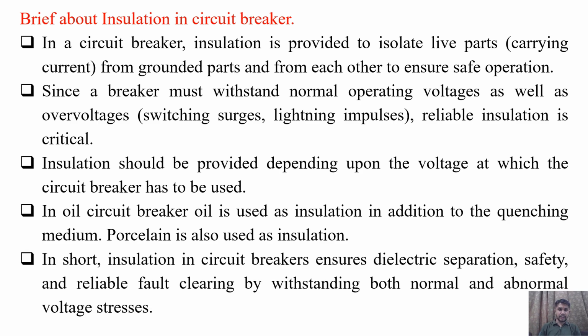In oil circuit breaker, oil is used as insulation in addition to the quenching medium. Porcelain is also used as insulation. In short, insulation in circuit breakers ensures dielectric separation, safety and reliable fault clearing by withstanding both normal and abnormal voltage stresses. So this is just a basic brief information of insulation available in circuit breaker.